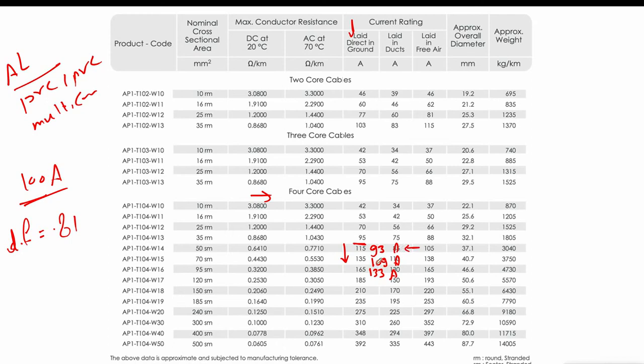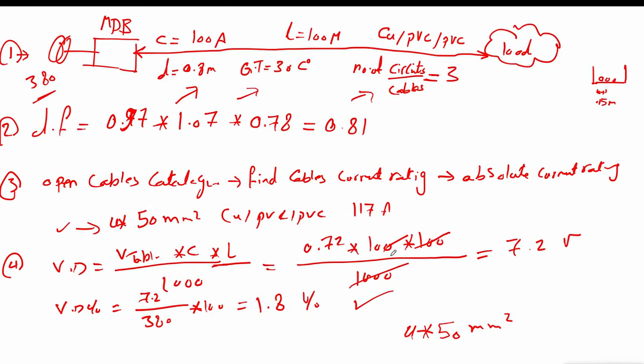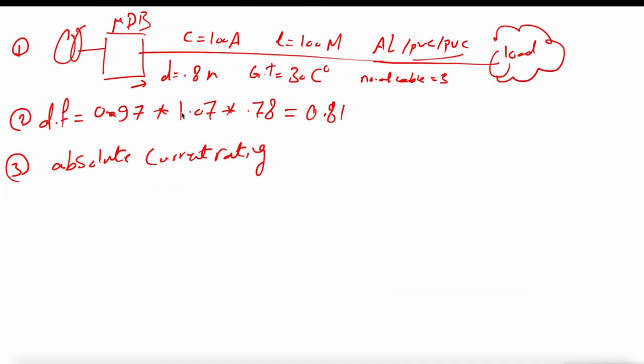The 50 sq mm cable is not acceptable. We select 70 square millimeters, which gives a derated current rating of 109 ampere — acceptable for our 100A requirement.